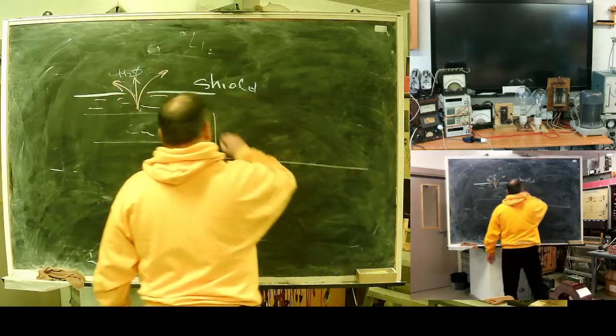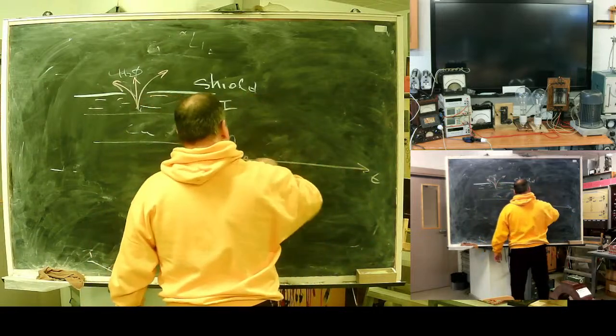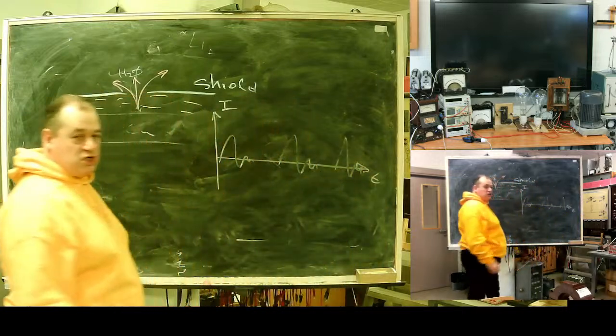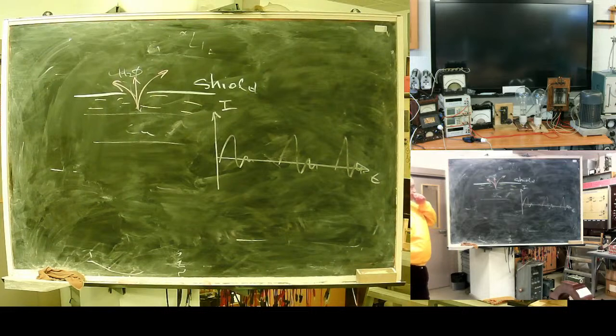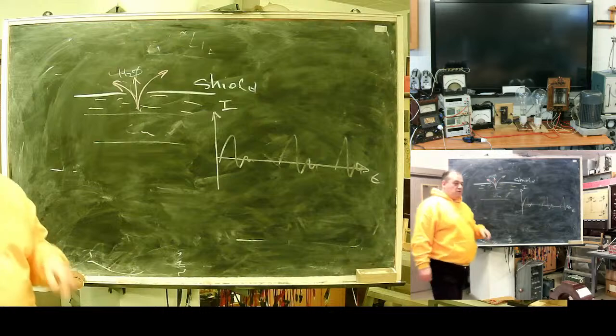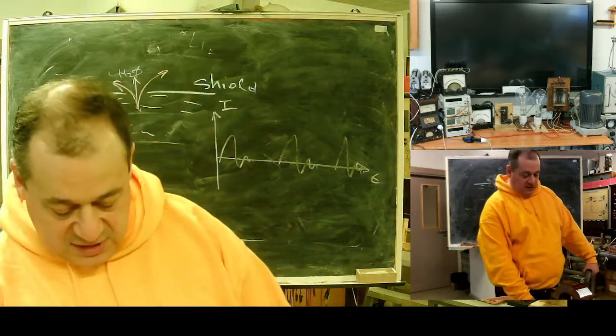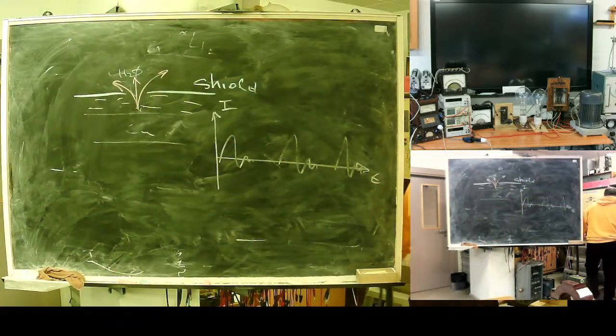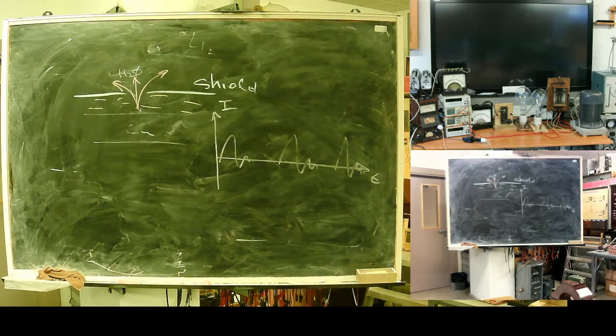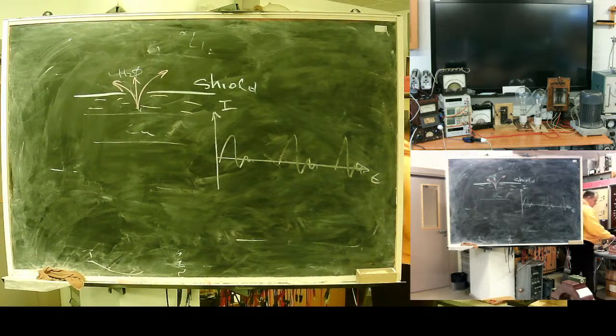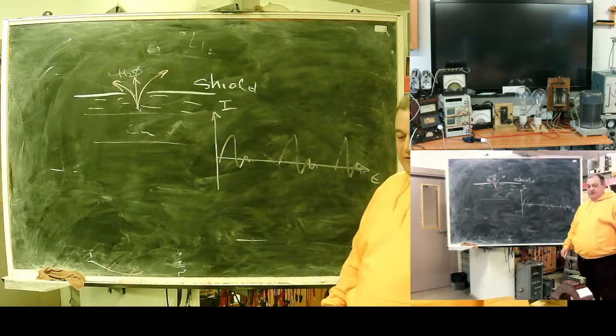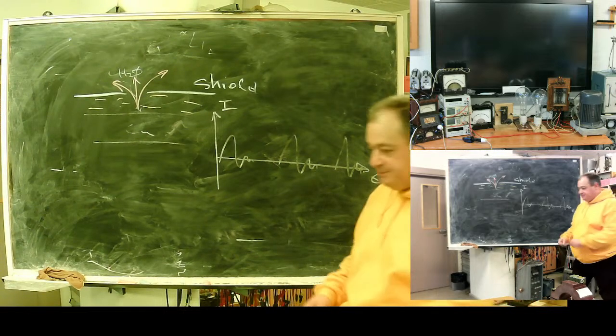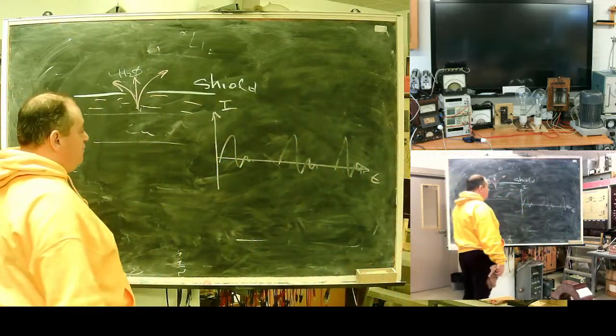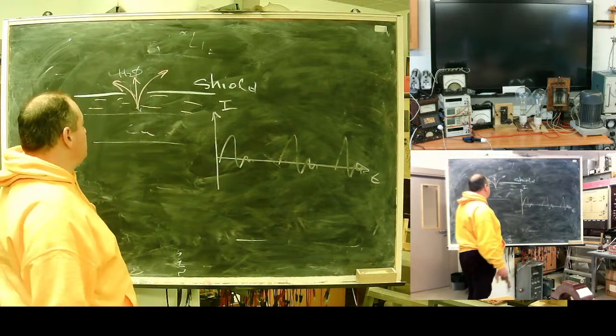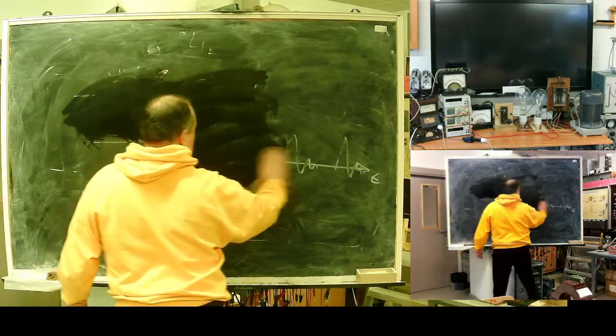Often, current of such fault looks like this. It shows there is often no constant current, but series of pulses. If you use simple, ordinary directed relay, it's highly possible that it will falsely return, and protection will never operate. So to prevent false operation due to intermittent arc, special measure should be taken, and its measure is a delayed return.